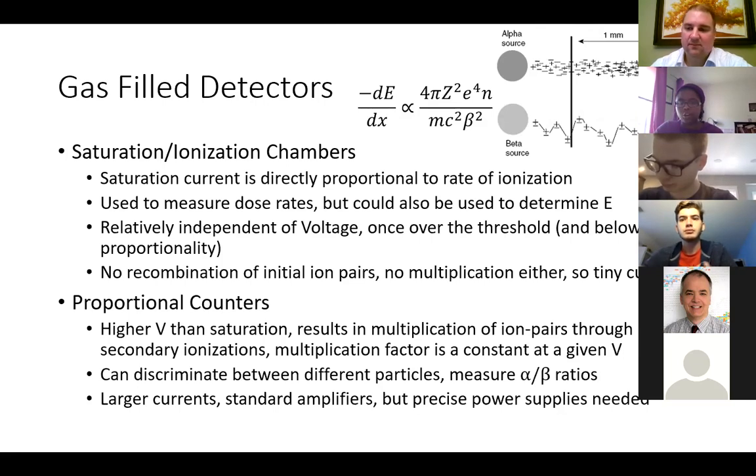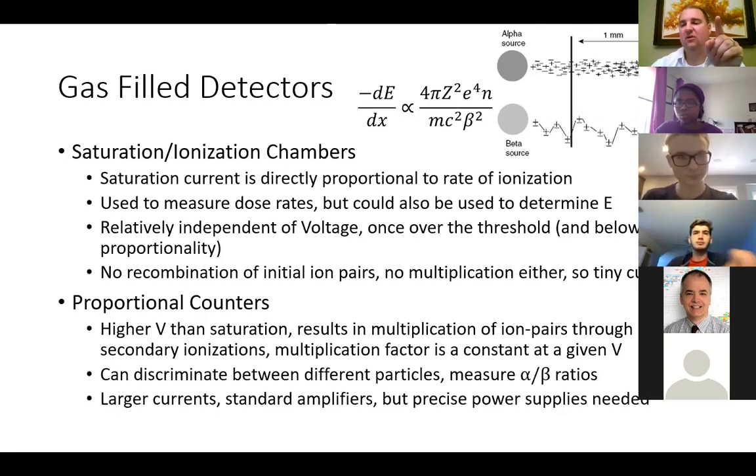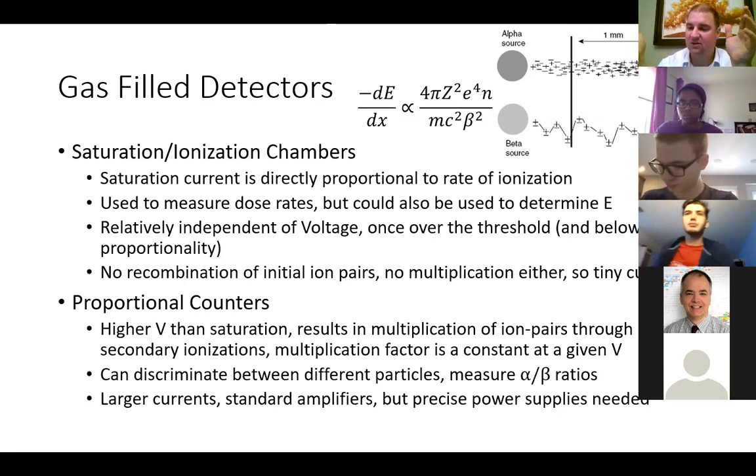By collecting charge, are you saying the detector measuring the count rate, or is that something else? The detector, when a single particle enters the detector, it's going to create ion pairs, create charge, deposit its energy in the form of charge, and all those electrons and all those ion pairs move towards the appropriate electrodes in the detector when there's applied voltage. And that all gets collected kind of all at once. And you can integrate that using capacitors and special kinds of circuit things. That's a little bit more on the electronics part.